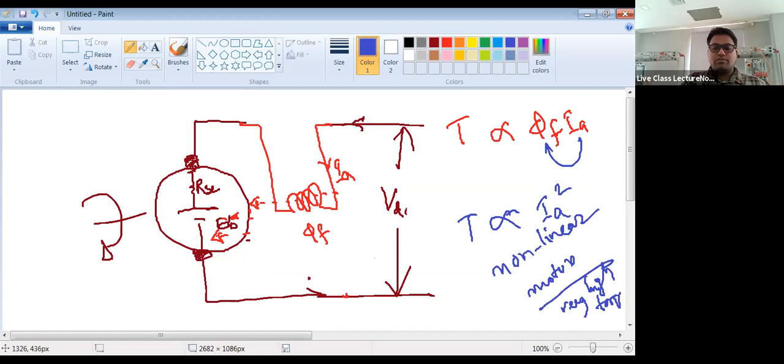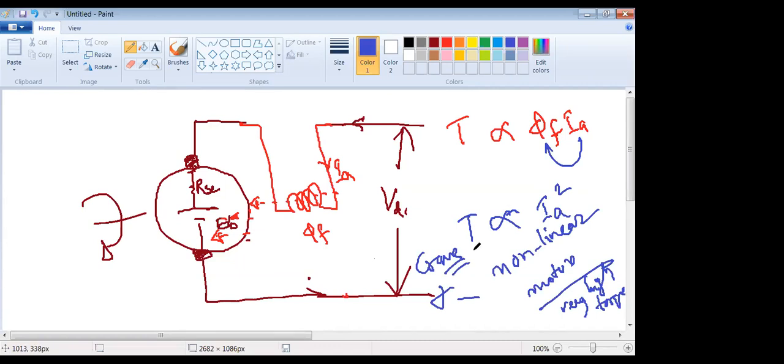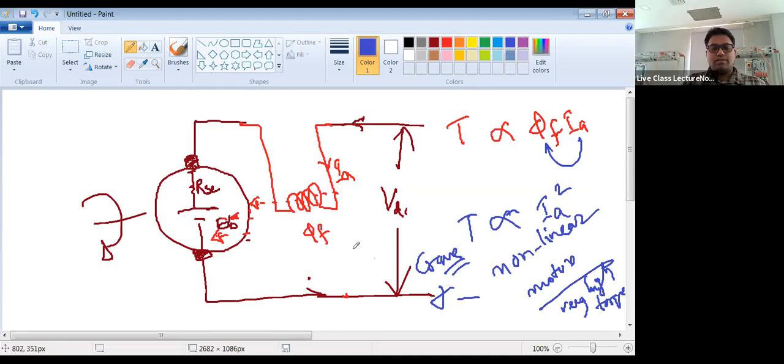Very high torque. So this is used in applications like the crane. It will just be on for a certain amount of time, say some seconds, and then it will be switched off. Right, and a series motor should not be started without any load. Say there is no load. If you start it, then the speed of this armature will be so much high within some seconds that the parts may fly out. Tell me one such application of this series motor in your day-to-day applications.